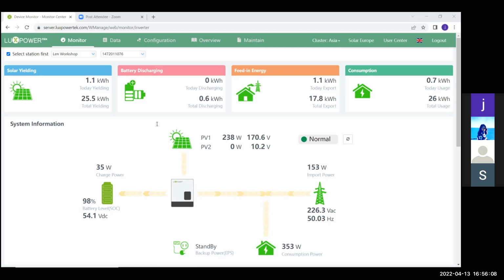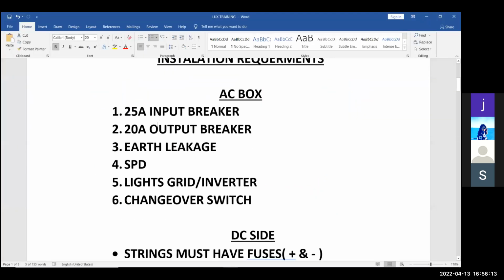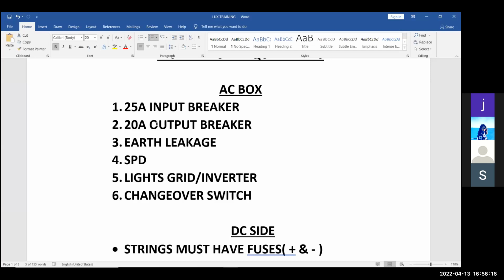Okay, for your installation on these machines, we require, not require, but we recommend that you have a 25 amp input breaker, a 20 amp output breaker, an earth leakage, an SPD, and lights to tell you if the inverter and the grid is on, so that you know where the power is coming from if you want to work on your house electrical system, so that you know the inverter is switched off, the power to the house, and so forth. Then as well, an important thing that we recommend is a changeover switch.